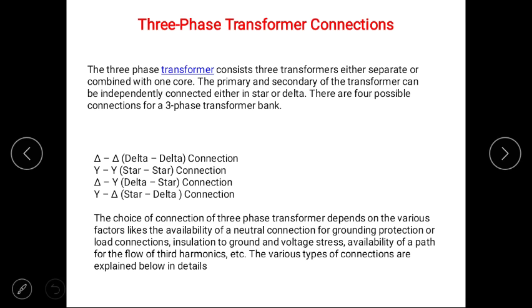The possible connections are delta-delta connection, star-star connection, star-delta connection, and delta-star connection. The choice of connection of a three-phase transformer depends on various factors like the availability of neutral connection for grounding, protection or load connection, insulation to the ground and voltage levels, and availability of a path for the flow of third harmonics.